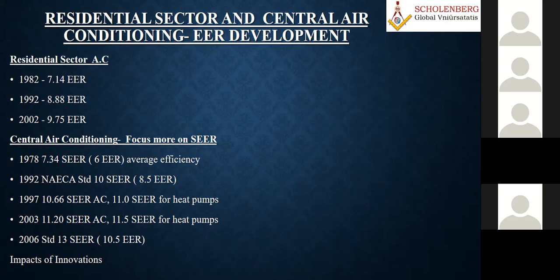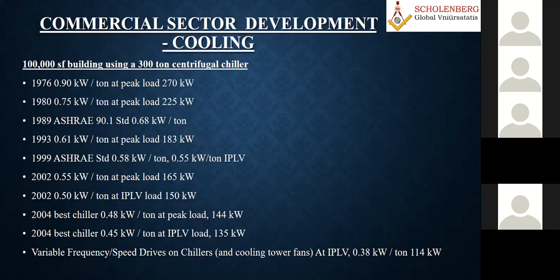When it comes to central air conditioning, we focus more on the seasonal energy efficiency ratio. You see that since 2006 it has come to even 13, isn't it? So this is much advancement and development.